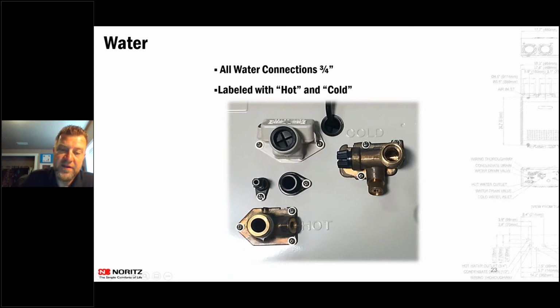If you look at the bottom of these, you'll see these little barbs. Those are drains. So if you did have to drain down the heat exchanger, you could put a small piece of tubing on, or just twist it. You twist it about halfway out, and it'll start draining through the middle of that. So you could actually drain down the heat exchanger if you were in a cabin situation or something like that, where you're going to winterize it. You can drain it out there.